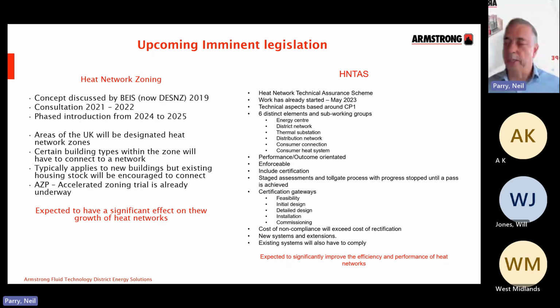So all areas really of a heat network. And it is a toll gate process, which basically means that as you progress through the build, you will get to points where the system as it stands has to be verified that it meets the requirements of the assurance scheme, and only then, when that's been assessed and approved, can you move on to the next stage in that design.